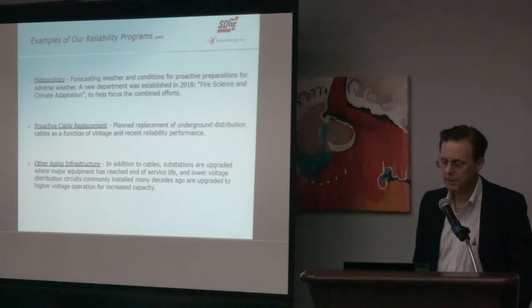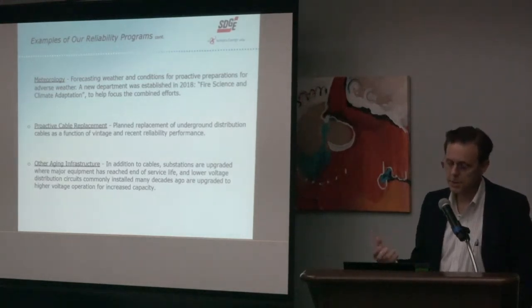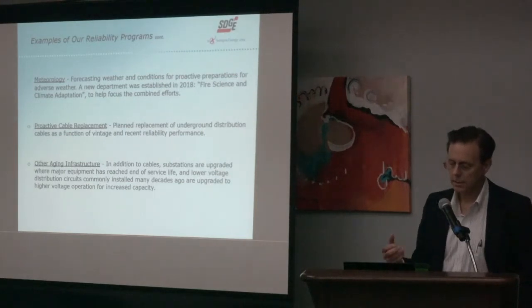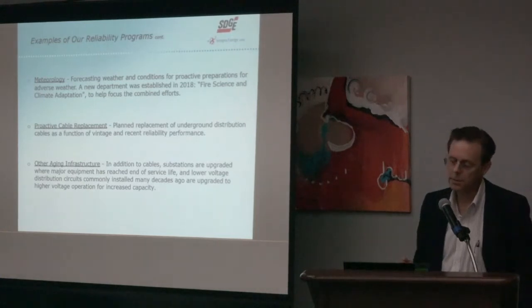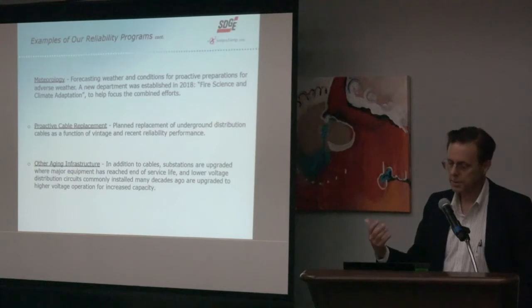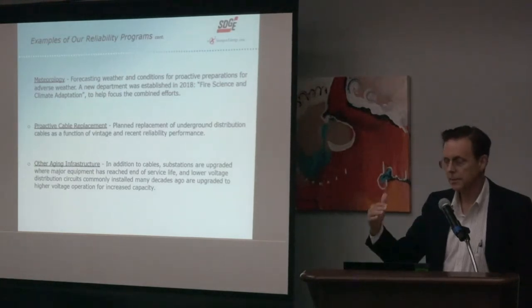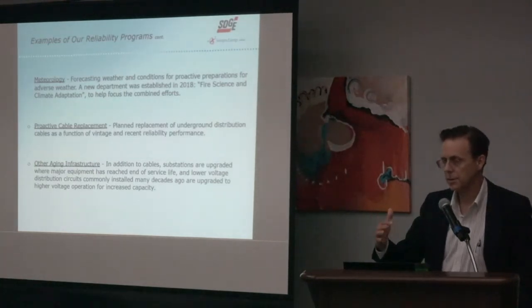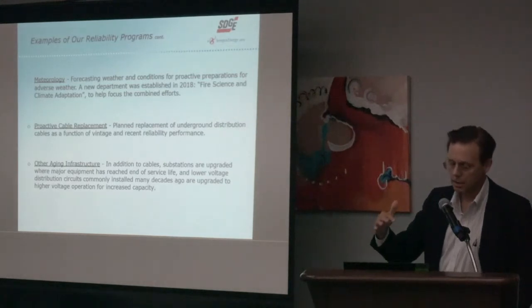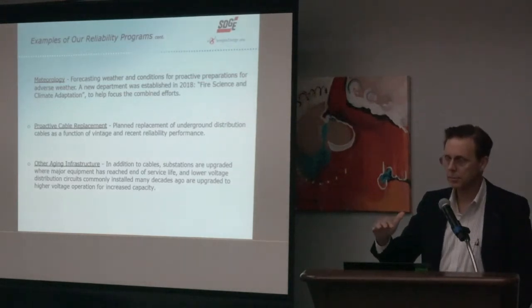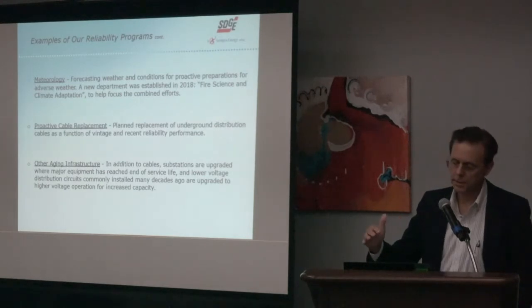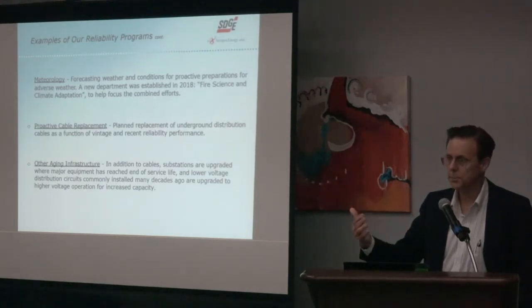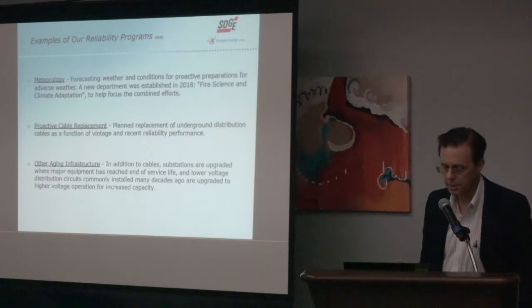We have other aging infrastructure in addition to cables. Substation upgrades are done to address the end of service life for substations, which again is maybe in the 40 to 50 year time frame. Lower voltage distribution circuits installed many years ago are often upgraded to higher voltage - older neighborhoods in urban areas were generally served from older 4 kV circuits. Now we like to upgrade those to 12 kV, getting much more capacity and much better voltage regulation from doing that.